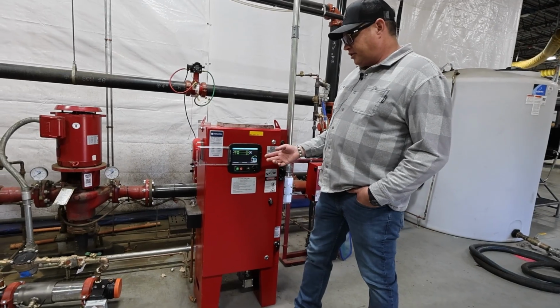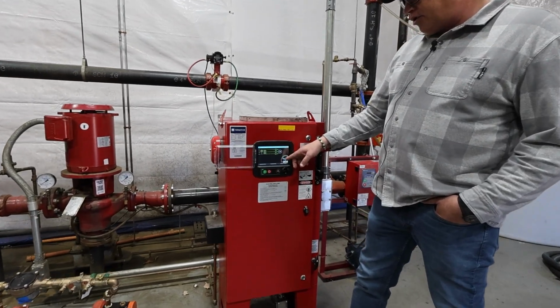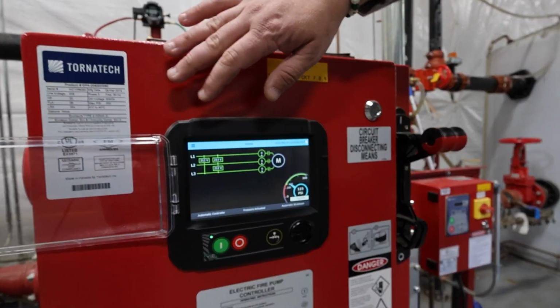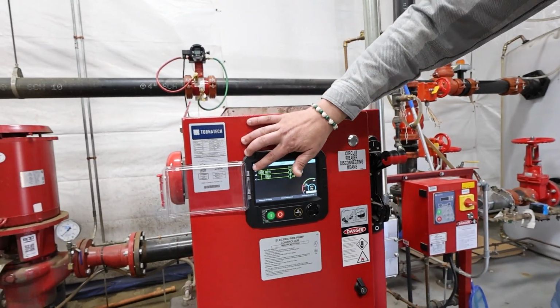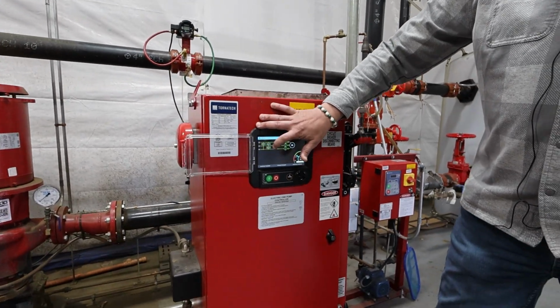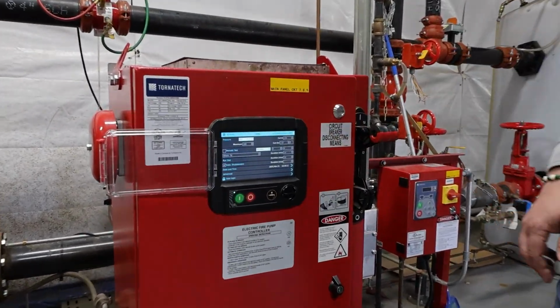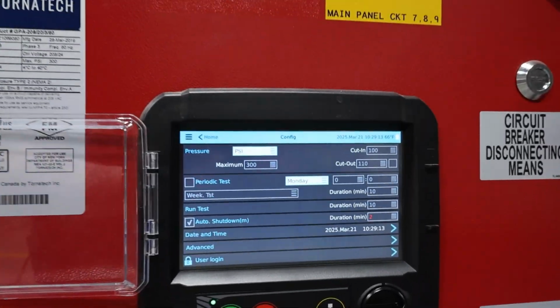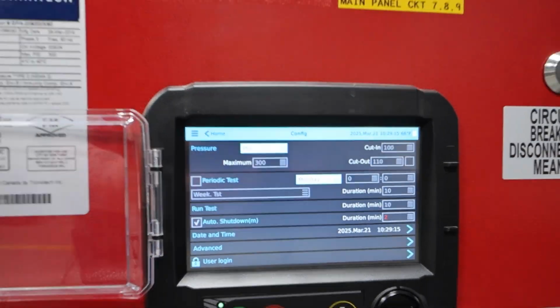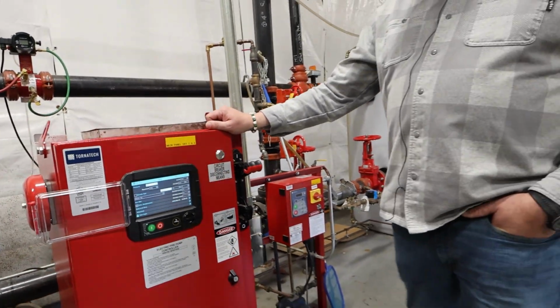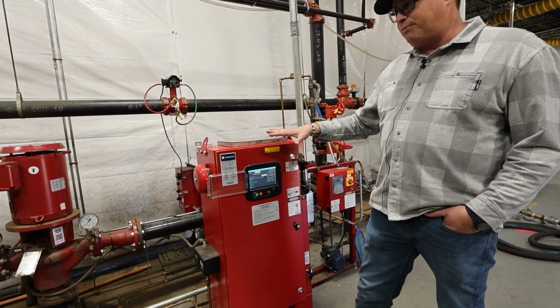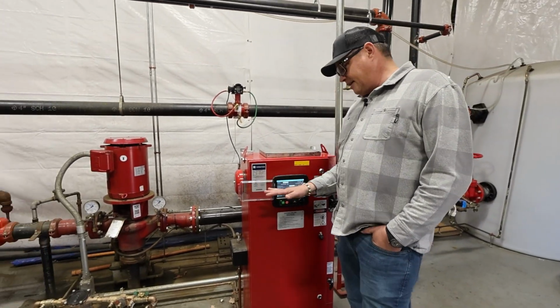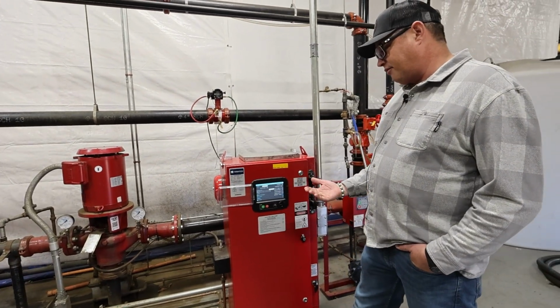So one of the things I'll do, I can see it here on the controller where my cut in and cut out is, but I'm gonna go up here to my little hamburger menu screen, check my settings, and actually see what it was actually set to, my cut in and my cut out. It's cut in at 100 and cut out at 110. So I know that this pump is currently pressurized to over 110 PSI, so the fire pump's not gonna run.